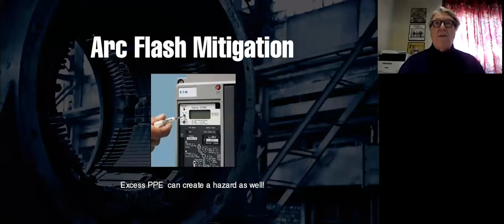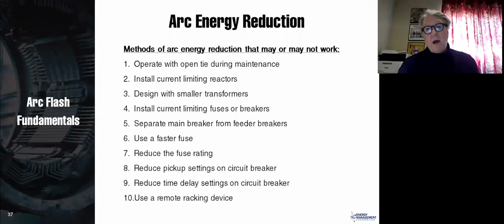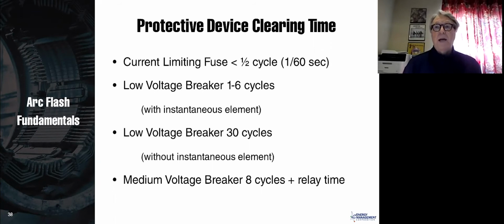Let's take a look now at arc flash mitigation. So we have an arc flash, and let's say that the gear is 30 calories. Well, we don't like 30 calories because none of us likes being in that beekeeper suit. So we look at arc flash mitigation. And in fact, the code now requires arc flash mitigation. I'm not going to discuss this, but these are some theoretical arc flash energy reduction methods that you could use that may work or they may not work. Some of them are pretty good, like using a remote racking device. That's pretty nice. What I'm going to do next is talk about the code, and talk about methods that actually do work.